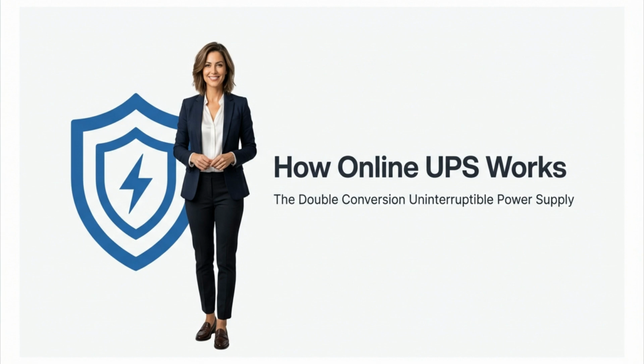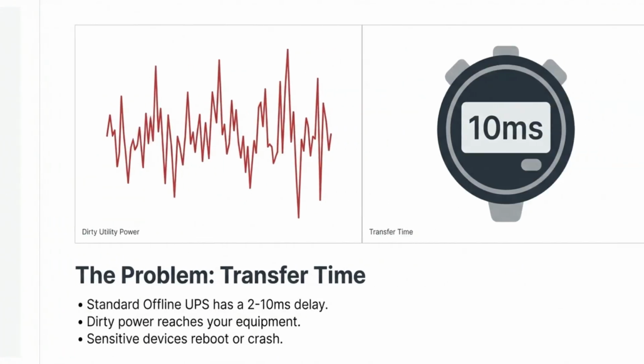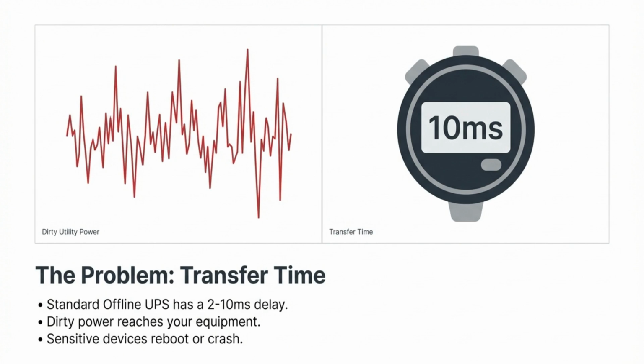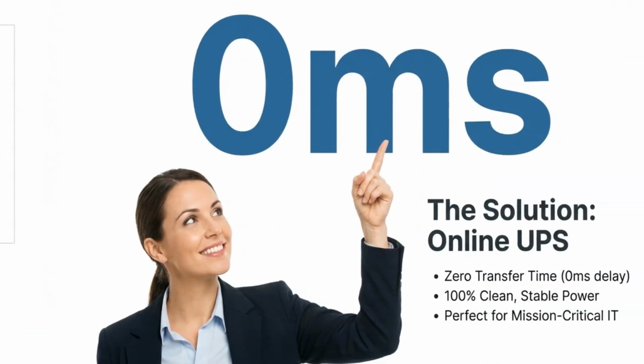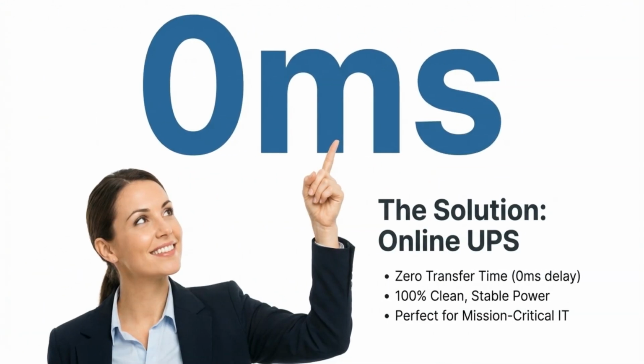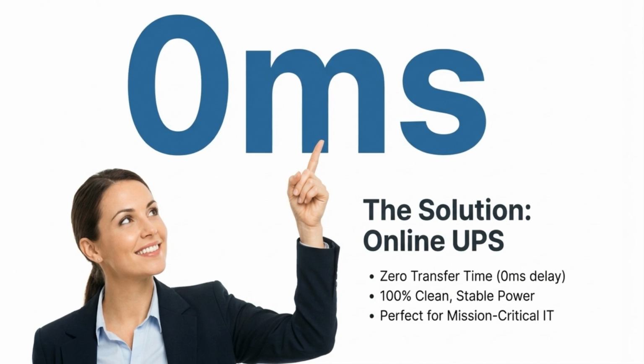Welcome to this video on how online UPS systems work, also known as double conversion uninterruptible power supplies. Standard offline UPS systems face a problem with transfer time, causing a 2 to 10 millisecond delay. This allows dirty utility power to reach your sensitive equipment, potentially causing reboots or crashes. The solution is an online UPS, which provides a 0 millisecond transfer time. This ensures 100% clean and stable power, making it perfect for mission-critical IT applications.